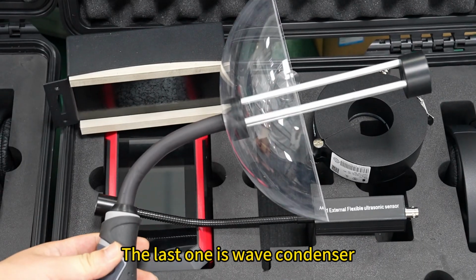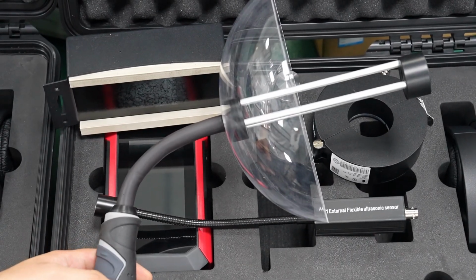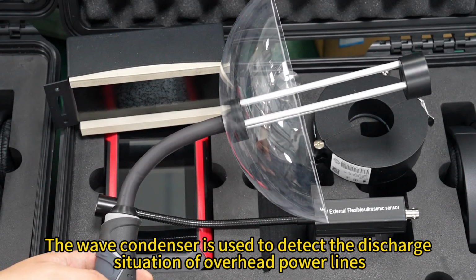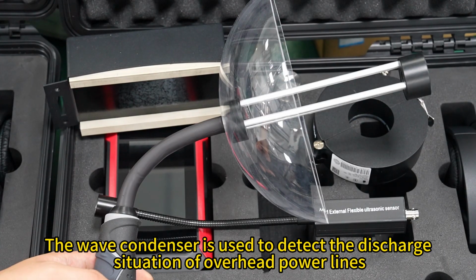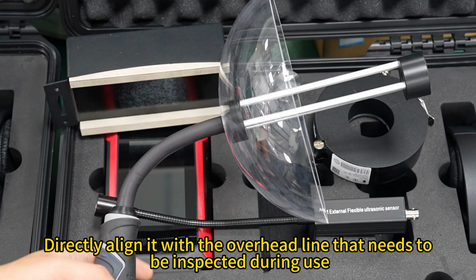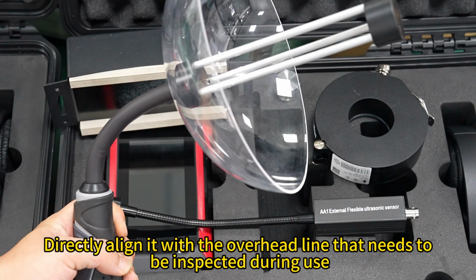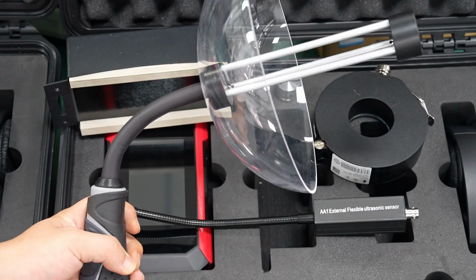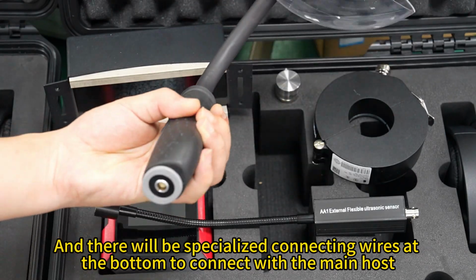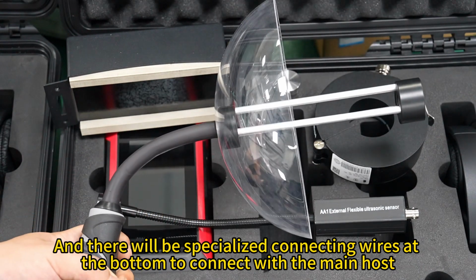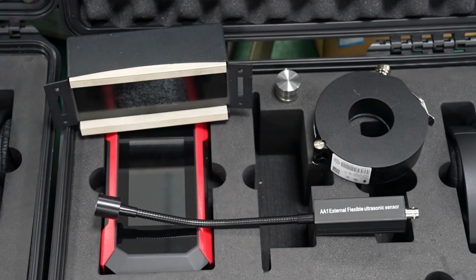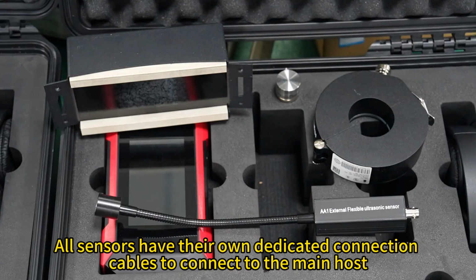The last one is the wave condenser. The wave condenser is used to detect the discharge situation of overhead power lines. Directly align it with the overhead line that needs to be inspected during use. There will be specialized connecting wires at the bottom to connect with the main host. All sensors have their own dedicated connection cables to connect to the main host.